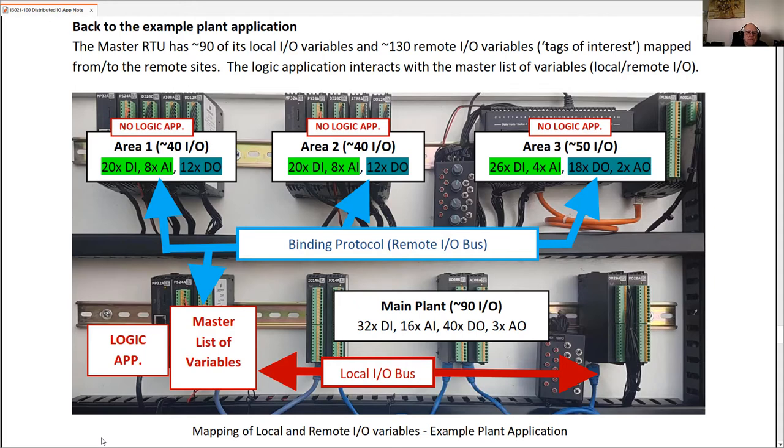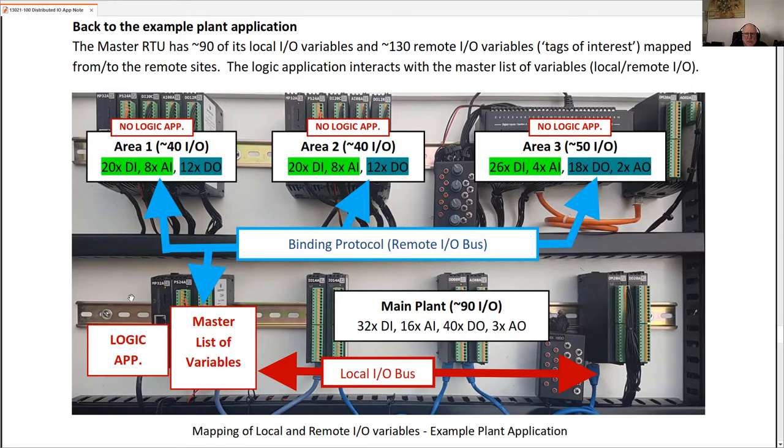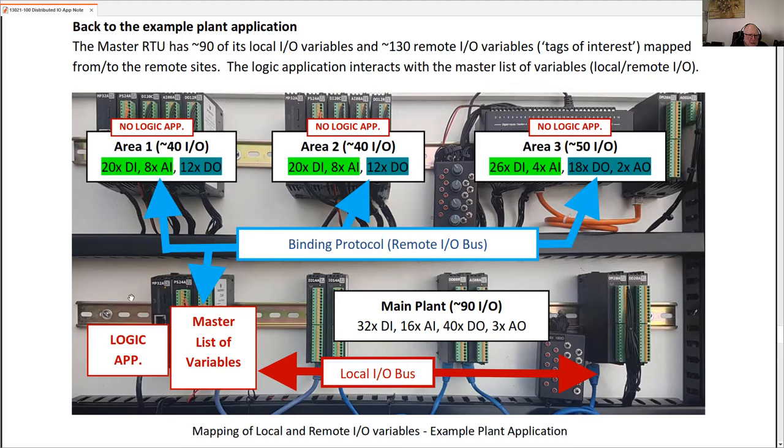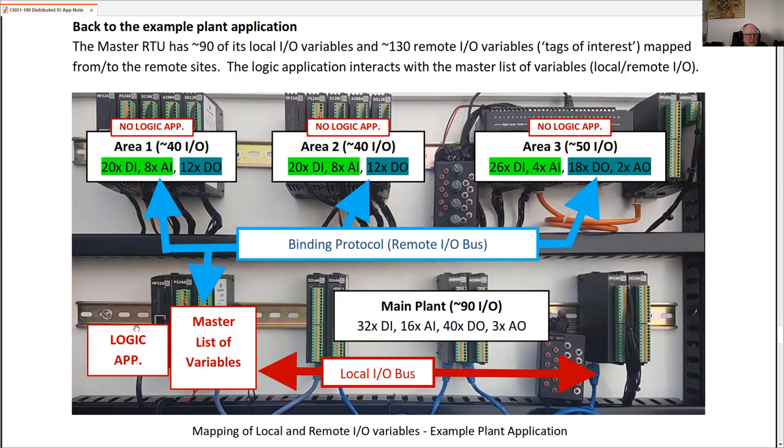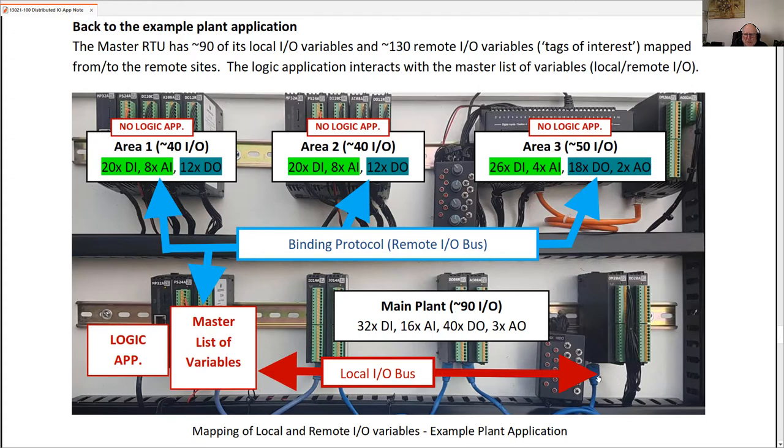The primary overview of our test example application that we have here. So in plant applications whether it's substation automation, solar farms, water and wastewater treatment plant type applications, there is usually a need for both distributed and remote I/O. So the objective here is to show that we can have this single logic application running in one of the RTUs. It has some distributed I/O on the local I/O bus, so it's stretched out to 15 meters and two more 10 meter segments. So we have a 35 meter local I/O bus here.